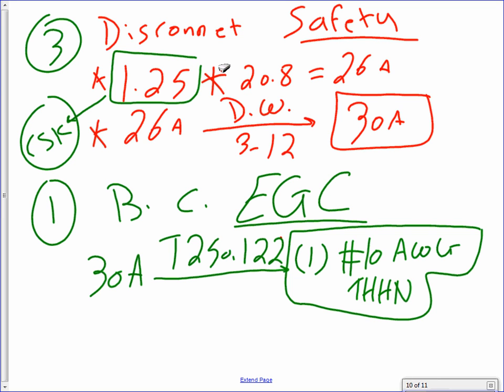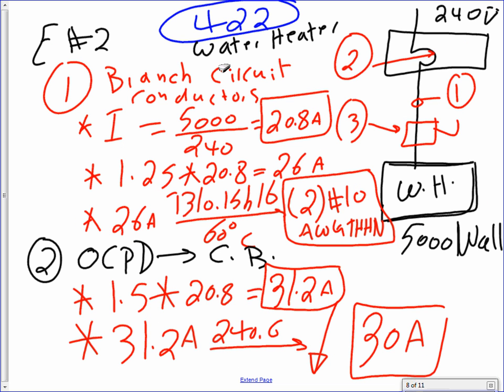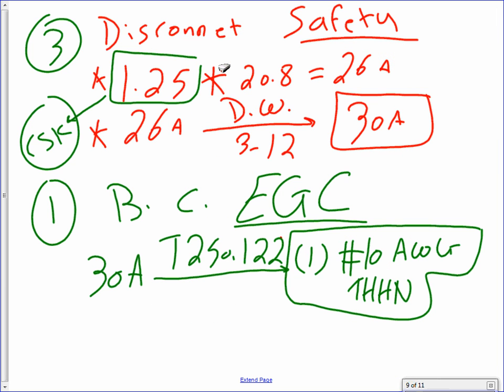Here's your branch circuit. Any comments, guys? Any questions? So we sized the branch circuit conductors, the overcurrent protection device, the equipment ground conductor and the disconnect. Any comments? Any questions? That's all I have for you. I will go over two examples like this as we move on, just to get it to stick. So when you size the water heater and came up with a 30 amp circuit, 2 conductors, number 10, that's how you should have done it. If you do the calculation for the water heater, you should come up with the same size. Okay, thank you.